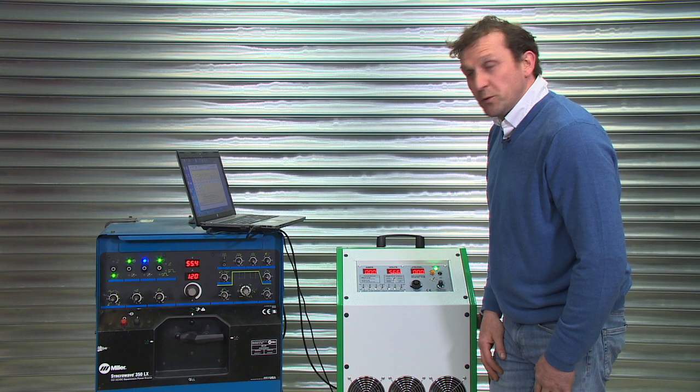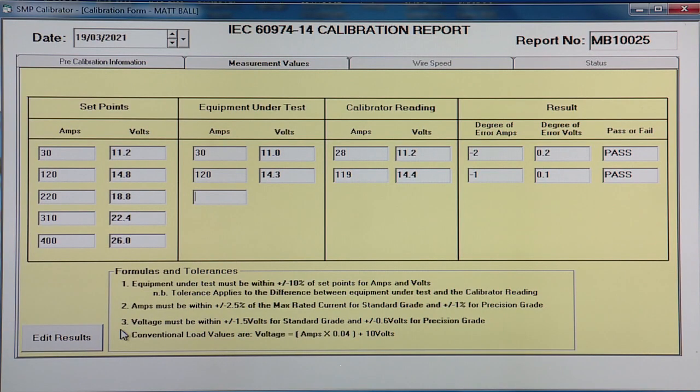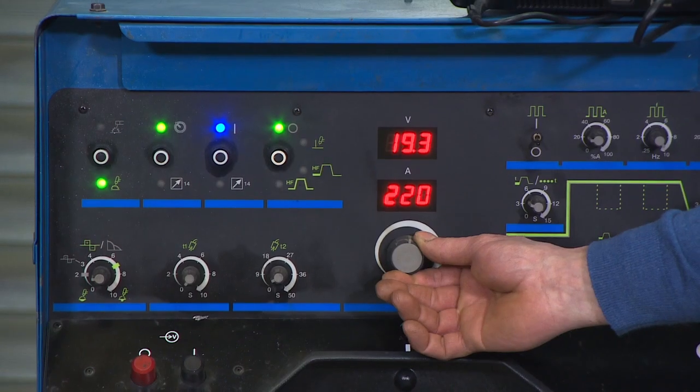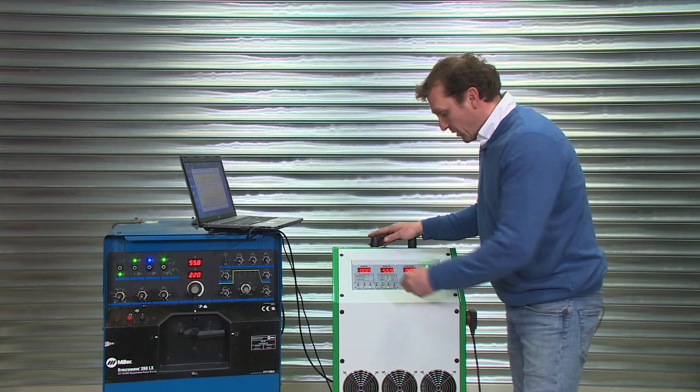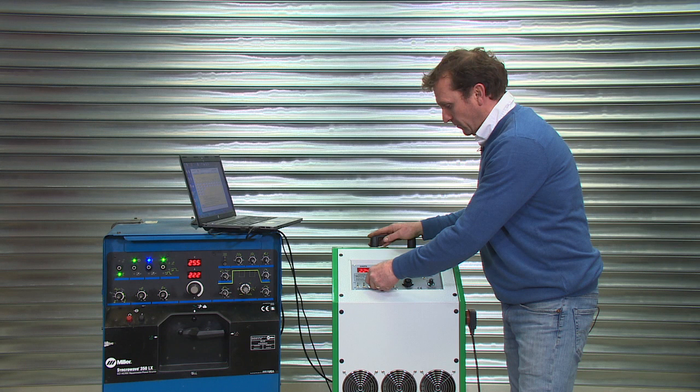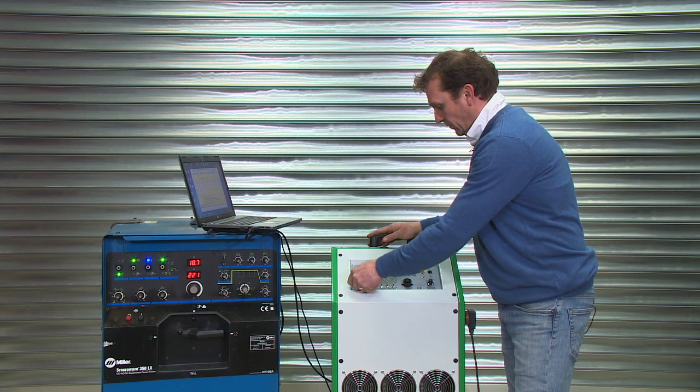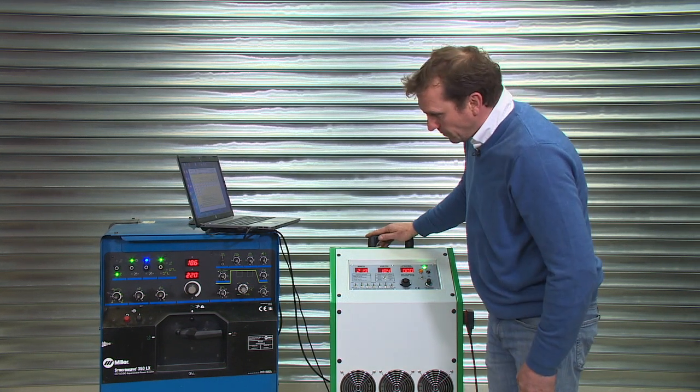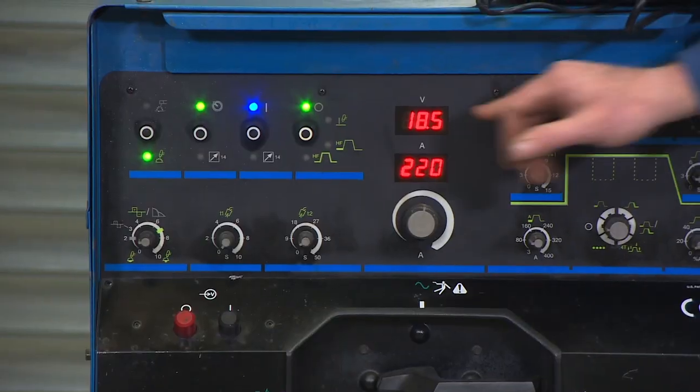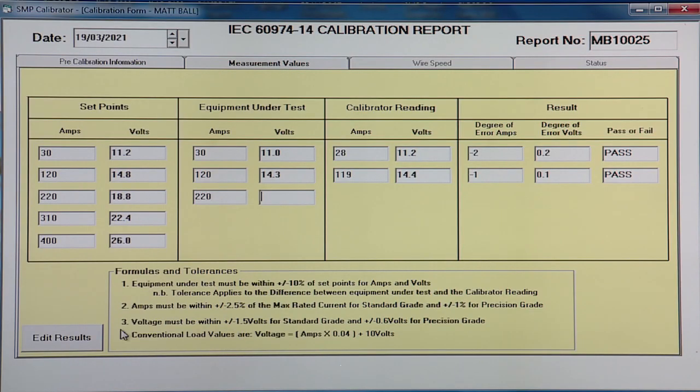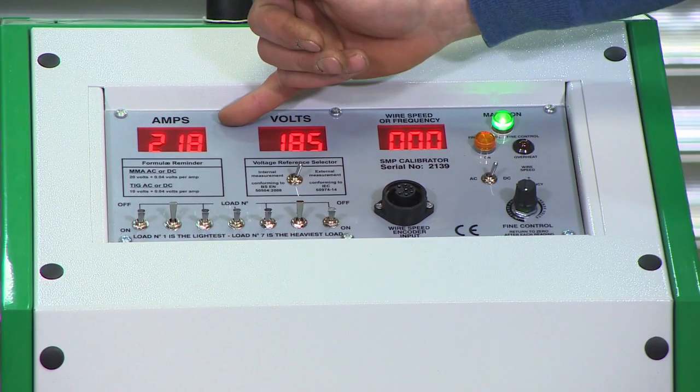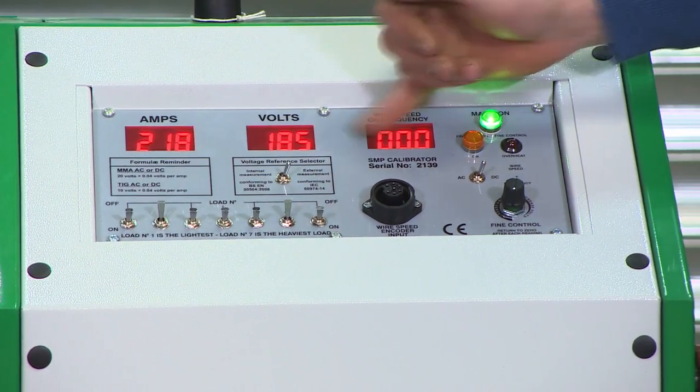Onto the next reading, 220 amps, 18.8. So we set the machine to 220. Then load up the calibrator to approximately 18.8 volts. We record 220, 18.5. Then the calibrator reading, 218, 18.5.